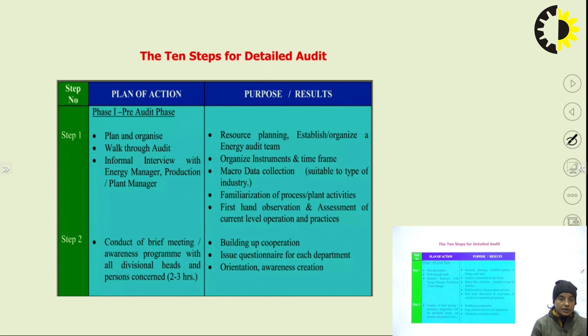So from step 3, the audit phase starts. In the audit phase, there is primary data gathering, process flow diagram and energy utility diagram. It will result in historic data analysis and base data collection, then process flow charts will be prepared, and all services utilities system diagrams, that is a single line power distribution diagram, water, compressed air and steam distribution, all these things will be prepared. Then design, operating data and schedule of operation will be collected, then the annual energy bill and energy consumption pattern will be collected.